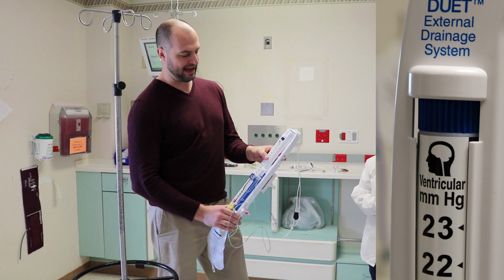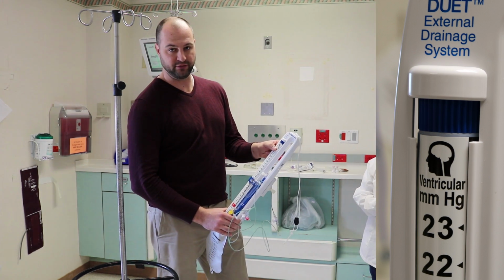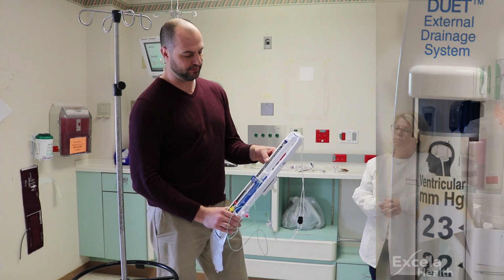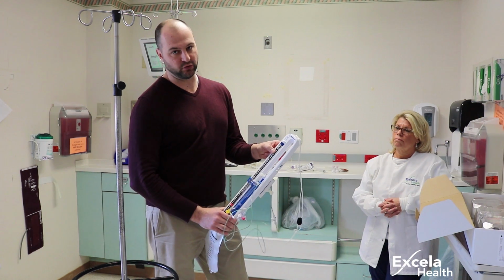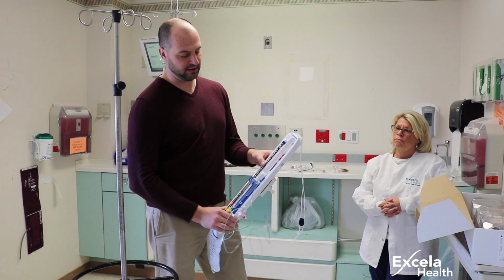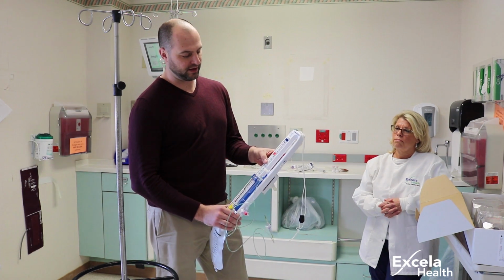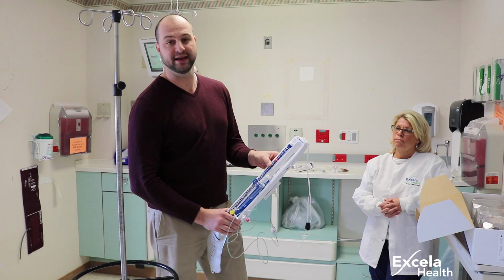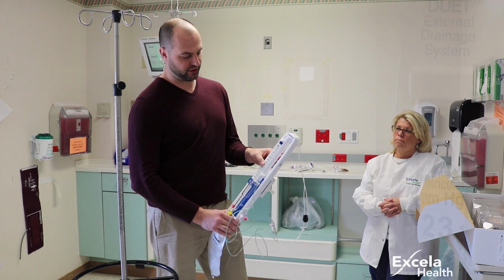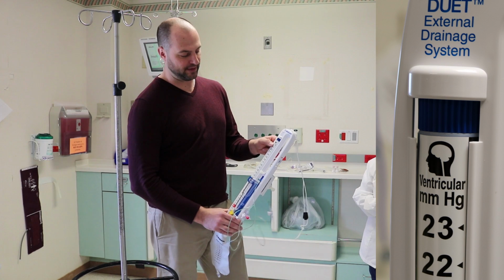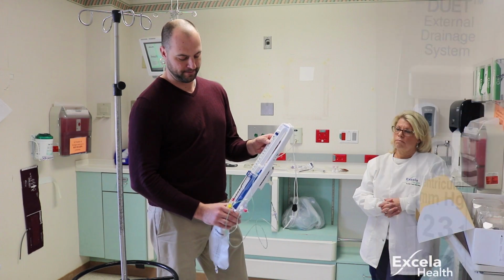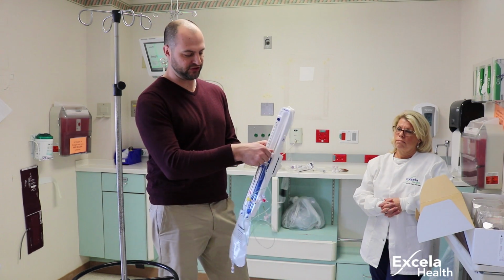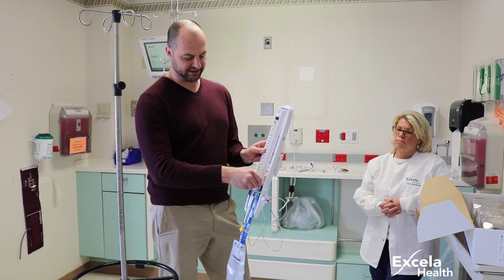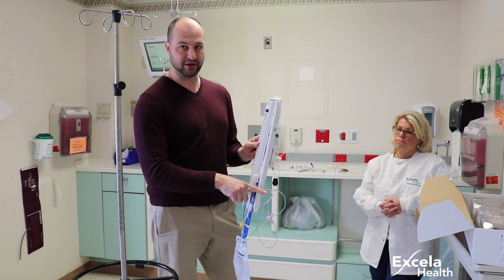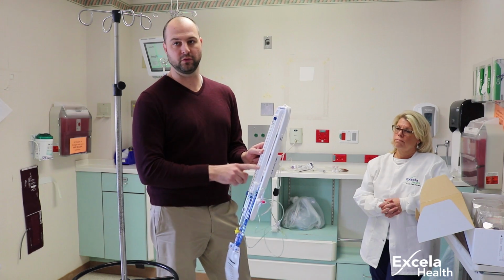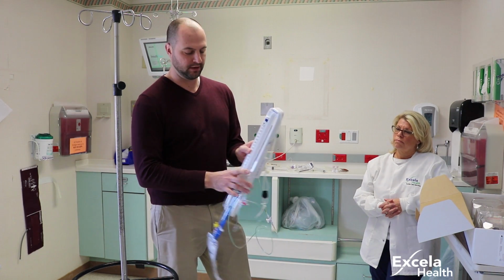It's labeled in black and white, and this is in millimeters of mercury, which is the reading that you would use here at the hospital. There is another option of using centimeters of water. Other hospitals may use that reading, and that gives you the flexibility to do so. Your other options are lumbar, millimeters of mercury, and centimeters of water. For this instance, you want to make sure that you are in the white scale with black numbers, the ventricular, millimeters of mercury. That will set you at 0, so that when I turn this knob and lower this to 0, it's lined up with the main system stopcock, and it gives you the millimeters of mercury reading on the scale.